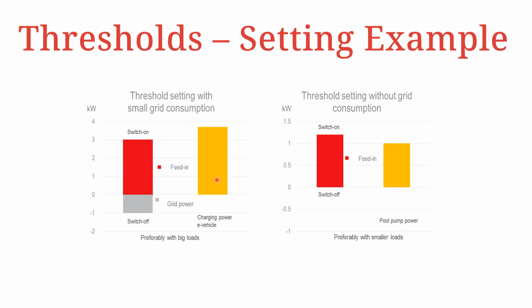Another example could be a threshold setting without grid consumption. This is preferable with smaller loads, something like a pool pump. Therefore, we have an activation threshold once we have about 1,000 watts. And if we have no surplus energy, then we are telling the inverter we do not want this load to be operating and therefore consuming from the grid. So at this point, we are switching it off from the 0 point, so we have no consumption at all from the grid as far as this load is concerned.